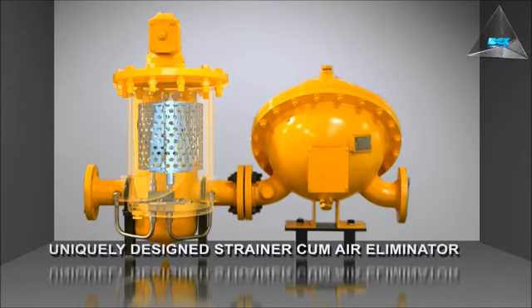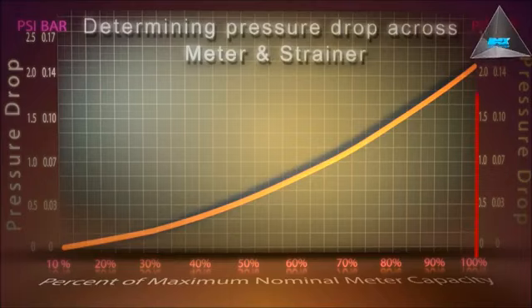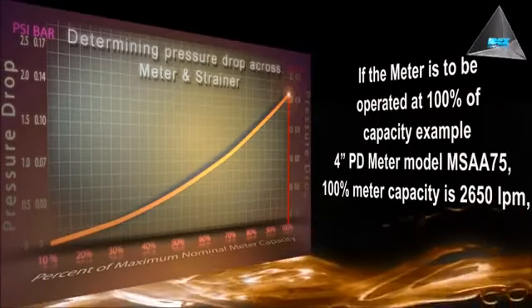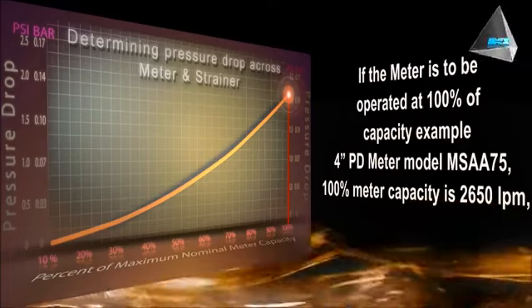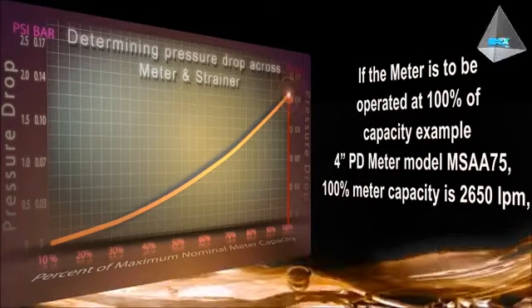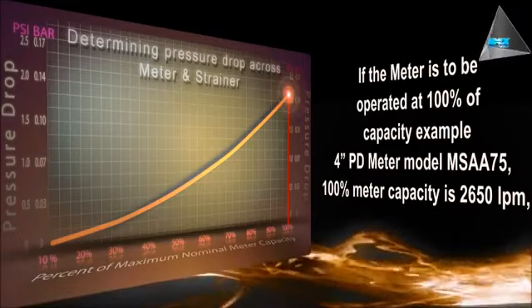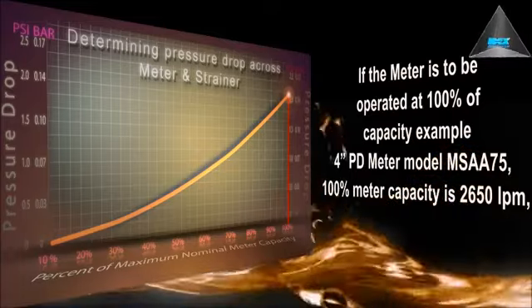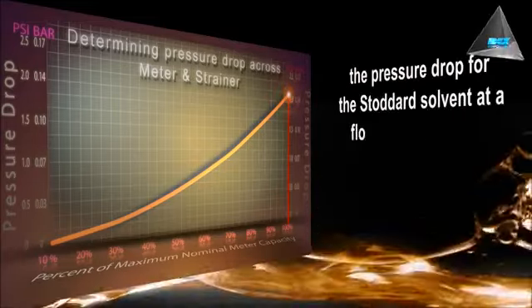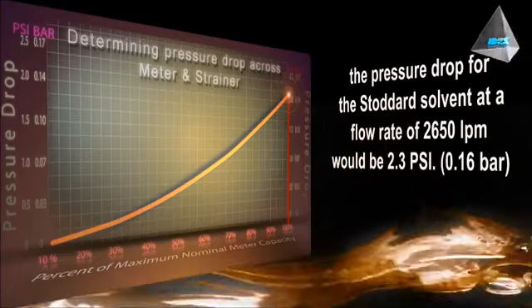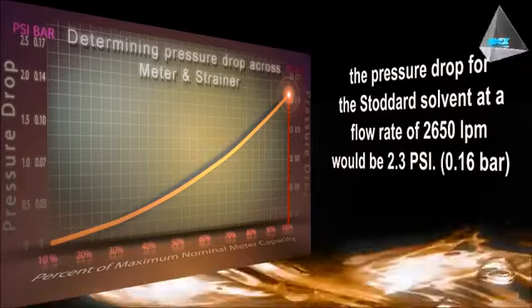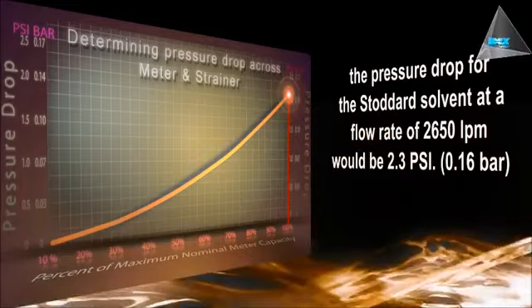The LC's unique strainer-cum-air eliminator design ensures a proper custody of measurement wherein the pockets of air at the final point of unloading from a compartment are vented and accurate measurement is ensured, determining pressure drop across the meter and the strainer. If the meter is to be operated at 100% of capacity, for example a 4-inch PD meter model MSAA 75, 100% meter capacity is 2650 liters per minute. The pressure drop for the Stoddard solvent at a flow rate of 2650 liters per minute would be 2.3 psi or 0.16 bar.